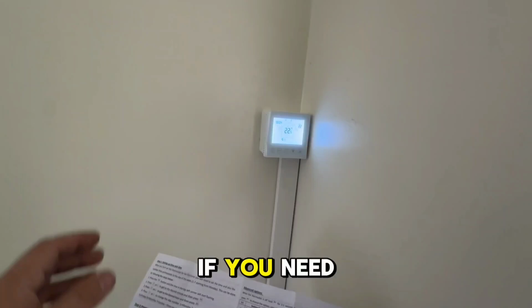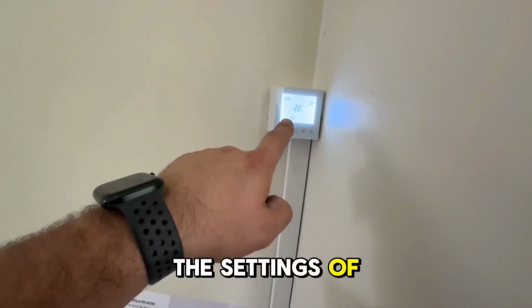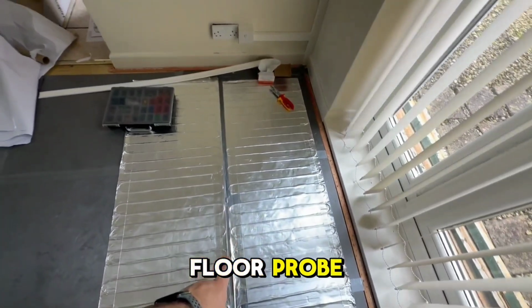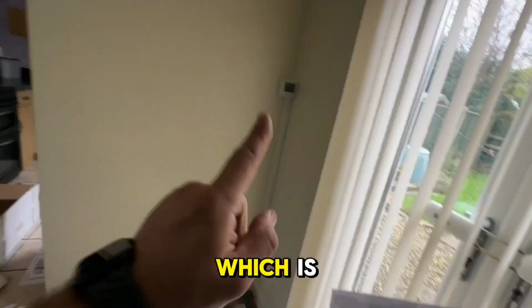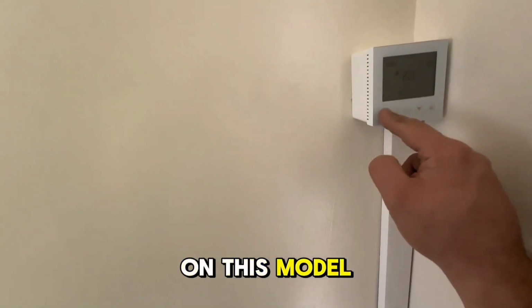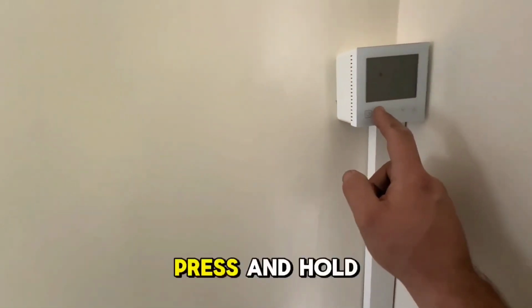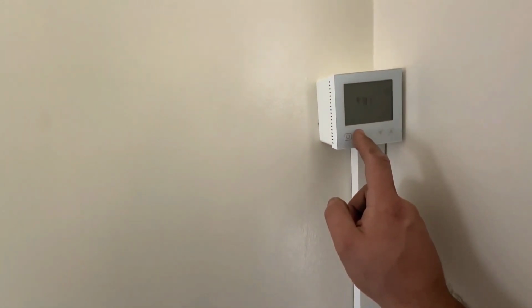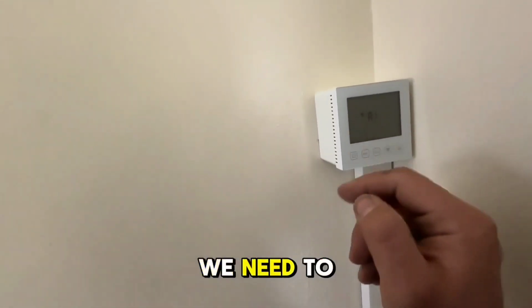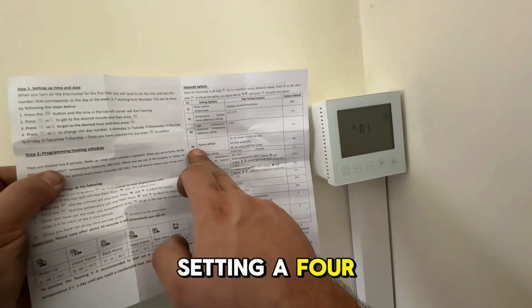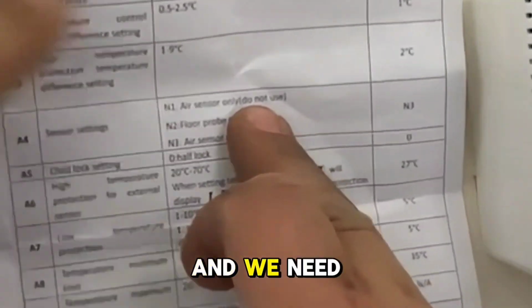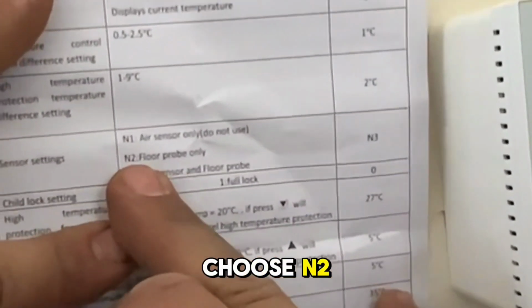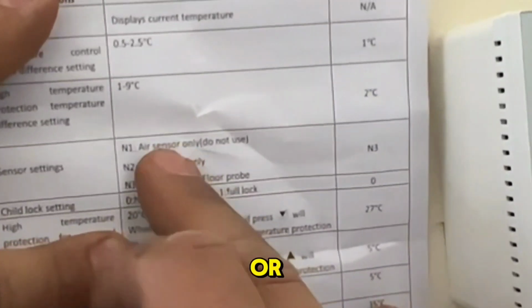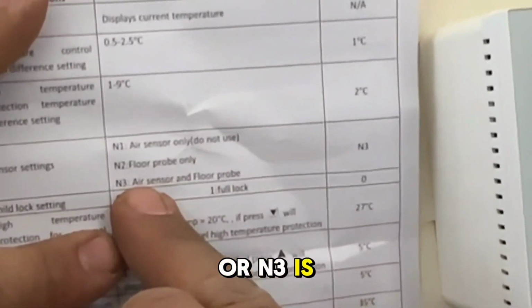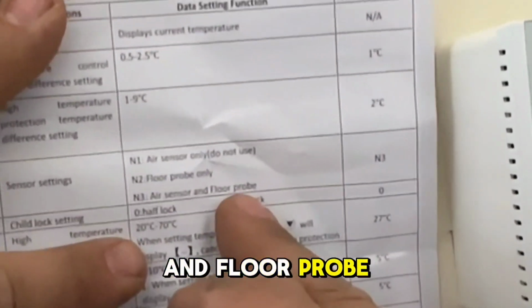And here we go. If you need to change the settings of your thermostat to make sure that it's reading floor probe and not the ambient temperature, which is very important, you need to, on this model in particular, turn it off, press and hold set for about 2 to 5 seconds. And we need to go to the setting A4, sensor setting, and we need to choose N2, floor probe only, or air sensor only, or N3 is air sensor and floor probe.